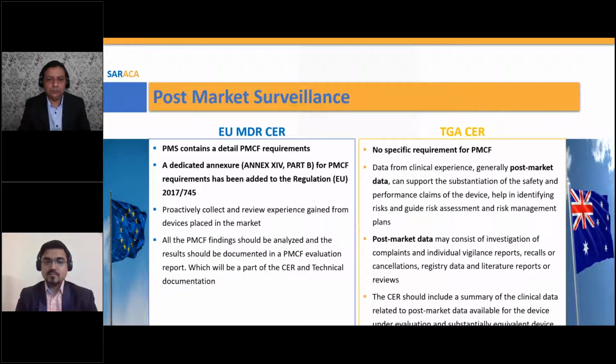The CER should include a summary of the clinical data in TGA related to post-market data available for the device under evaluation and for the substantially equivalent device. In the EU, all the PMCF findings should be analyzed, and the results should be documented in a PMCF evaluation report, which will be part of the CER and technical documentation. If you'd like to elaborate somewhat on this, Arun, this would be great.